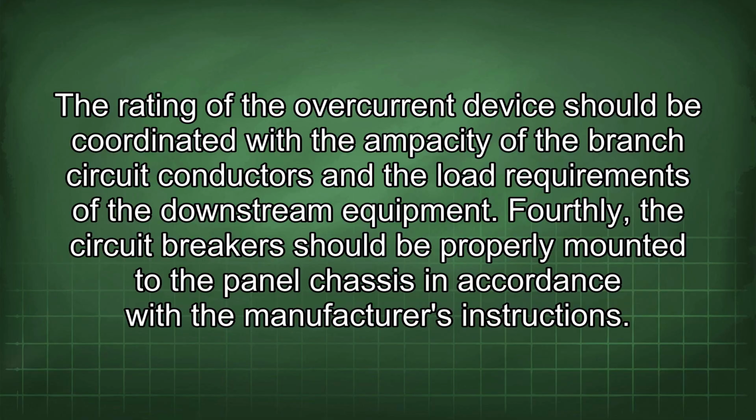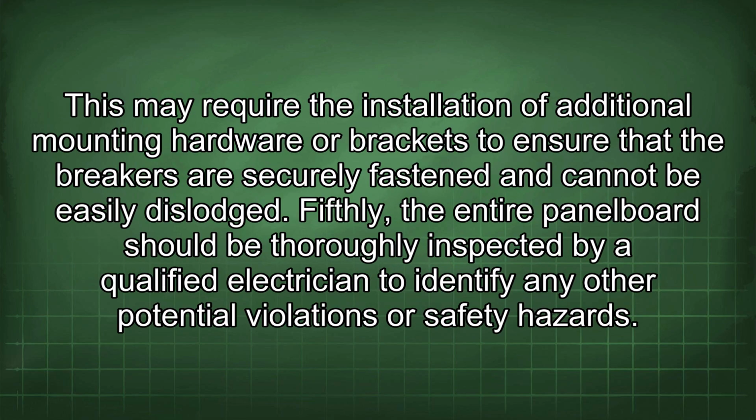Fourthly, the circuit breaker should be properly mounted to the panel chassis in accordance with the manufacturer's instructions. This may require the installation of additional mounting hardware or brackets to ensure that the breakers are securely fastened and cannot be easily dislodged. Fifthly, the entire panel board should be thoroughly inspected by a qualified electrician to identify any other potential violations or safety hazards.